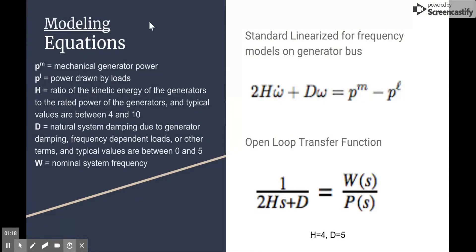Our system model has a couple of parameters. Basically, on the right side of our equation, we have the mechanical generated power, PM, subtracted by the power drawn by the loads. So essentially, this right side of the equation gives you the difference of these two powers, and that way it can be used to monitor the system. As you see, there's two coefficients, H and D, on the left side. H stands for the ratio of kinetic energy of the generators to the rated power, and these values are typically between 4 and 10. D refers to the natural system damping, or generator damping, and is typically between 0 and 5.